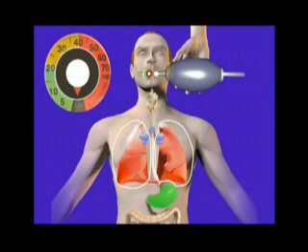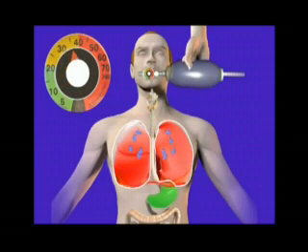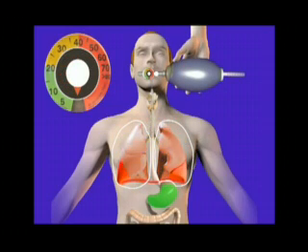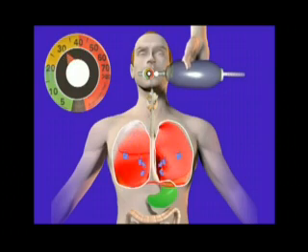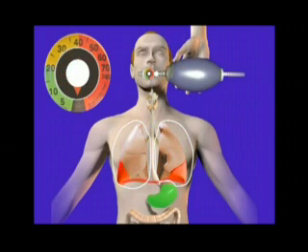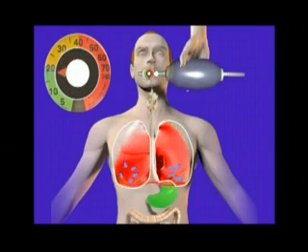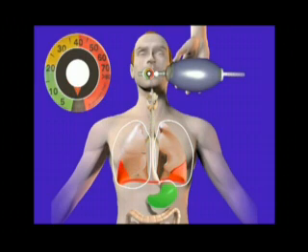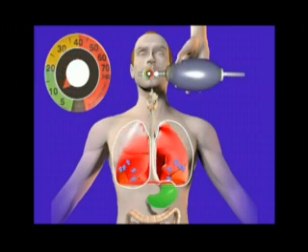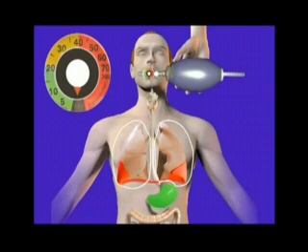Use of an integrated manometer can be an effective diagnostic tool. If pressure requirements change while ventilating a patient, it can be an indication of serious physiological changes such as pneumothorax, tension pneumothorax, or pulmonary edema. It can also indicate other issues such as an occluded endotracheal tube or tube migration.